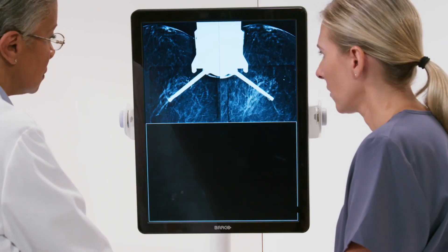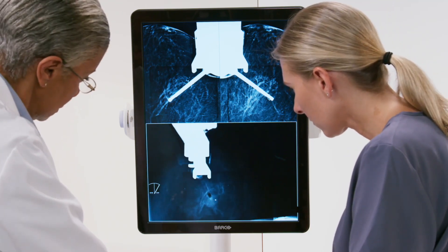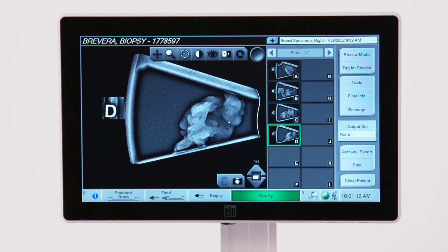One final tomosynthesis image is taken to confirm the marker is properly positioned and the procedure was a success. While the technologist focuses on the patient, the physician can review images on the Brevera system using a variety of tools such as zoom, contrast, and circle functions. Calcifications can be tagged for future reference and DICOM images can be archived to a PACS device, exported, or even printed directly from the workstation. The samples are seamlessly transferred to pathology with minimal handling to help maintain core integrity.